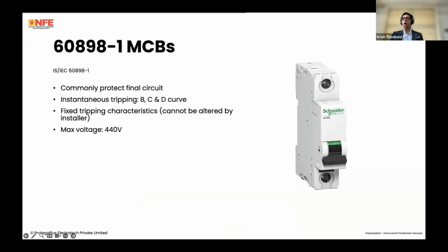Okay, the first product is the humble MCB, the 60898 MCB. In India, we have a standard, IS/IEC 60898 Part 1. That's for alternating current MCBs. These commonly protect final circuits, lighting circuits, socket circuits, perhaps water heaters, air conditioners, and so on and so forth. These have fixed tripping characteristics. That means that they cannot be altered by the installer. So we've got our type B, C, and D curve.